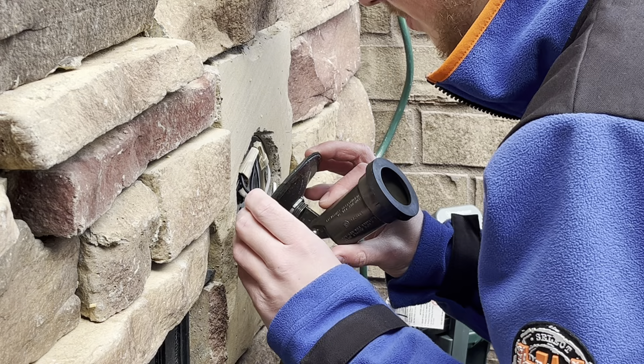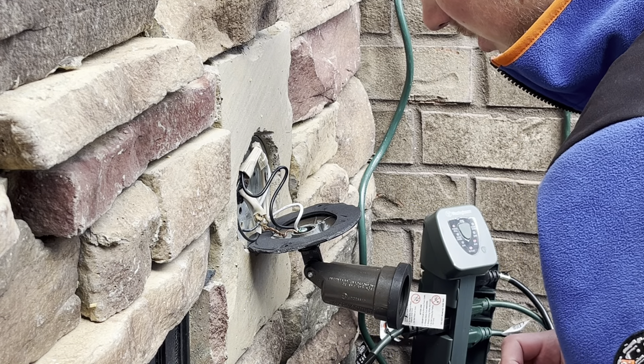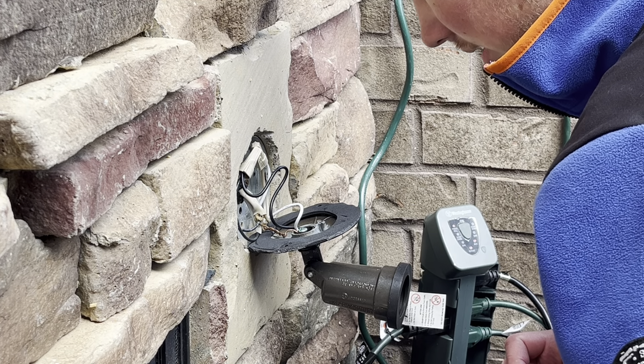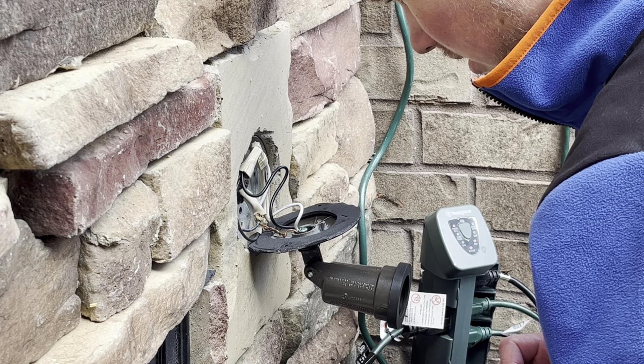Let's go ahead and pry this open again — we'll just tilt this back. It looks like it's been doing a good job keeping the water out, because I don't see any new rust marks inside the pancake junction box, so that's good.